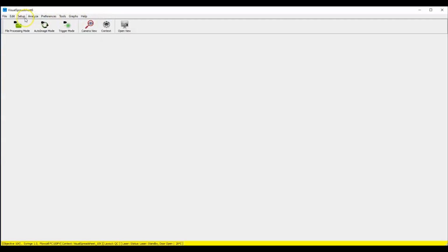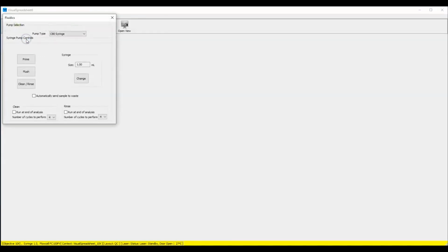To install the pump syringe, you will go to Visual Spreadsheet's main window, and from the Setup menu, choose the Fluidics option. This will open the Fluidics dialog box where you will find the Change button. When you click on the Change button, a Change Syringe dialog box appears, asking you if you want to change the syringe.